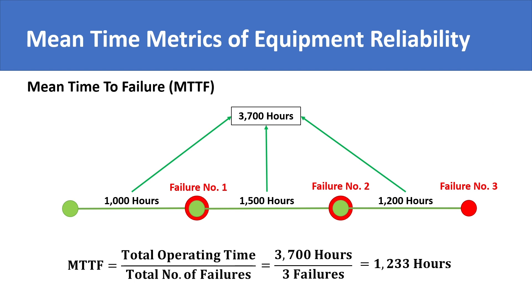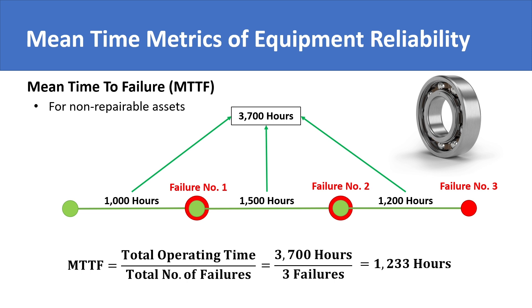Mean time to failure is exactly the same concept as mean time between failures. The only difference is that mean time to failure is for things that are non-repairable, such as a ball bearing. Once they fail, they are replaced. The rest of the concept is the same — wherever we mention the asset was repaired, we say it was replaced.